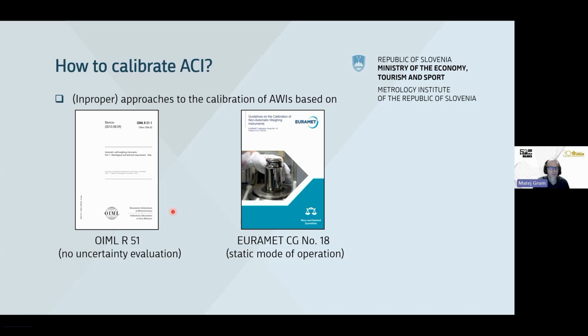The question was how to approach the calibration of automatic catchweighing instruments. At least in Europe, we noted two different approaches. The instrument was calibrated according to the legal metrology OIML guide or recommendation number 51. But the problem with this approach is that this guide doesn't take into account any uncertainty evaluation. On the other side, there is a EURAMET guide dedicated for calibration of non-automatic weighing instruments, but the instruments are calibrated in static mode of operation. But we'll see that there is an important difference between static and dynamic mode of operation.